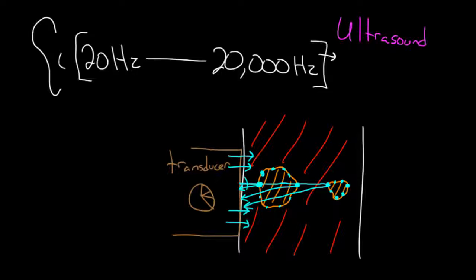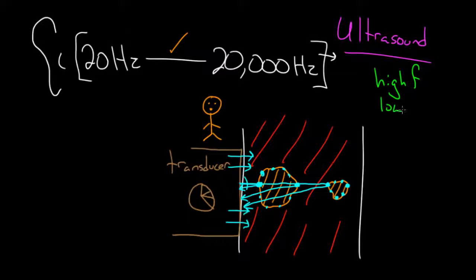It actually uses ultrasound frequencies. You might wonder why we have to use ultrasound. Well, one reason is if you took this transducer and you were using audible frequencies, you take this noisy thing, you hold it up to a patient, that patient's going to be like, you sure that's okay to hold up to me, doc? So that might be upsetting. But another more practical reason for using ultrasound is high frequencies, and that is to say low wavelengths. And these two are the same because remember, speed of a wave is wavelength times frequency. So if the frequency is high, the wavelength is low, because the speed's not determined by either of those, the speed is determined by the medium itself.